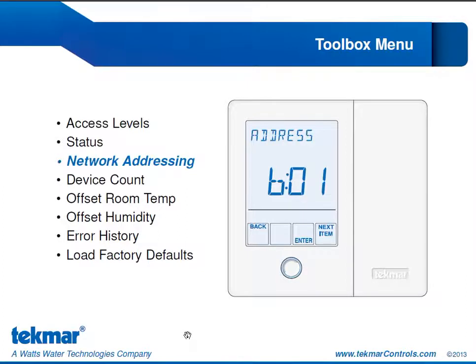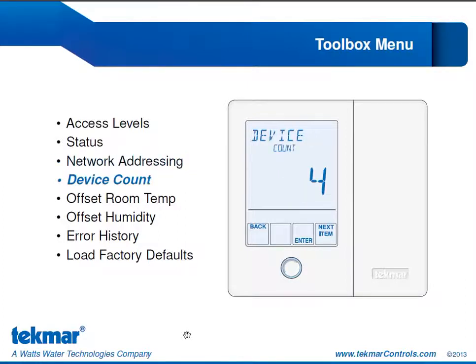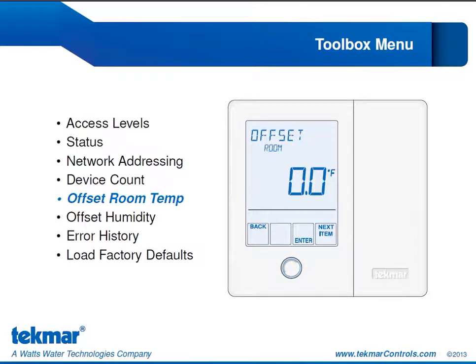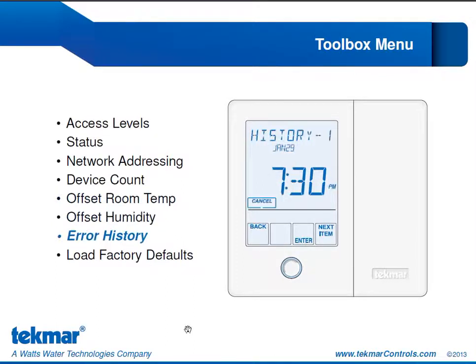The toolbox menu is where we can find the addresses for the 557. Also where we can find the device count. So this is telling us how many thermostats and set point controls the 557 is currently communicating with. In the toolbox menu, we can also offset the room temperature. So if we've installed the 557 in a location where it might be subject to airflow that is resulting in an inaccurate measurement of the room temp, then we can offset it by either 5 degrees below all the way up to 5 degrees above the actual measurement. Likewise, we can offset humidity from minus 10% all the way to plus 10%.